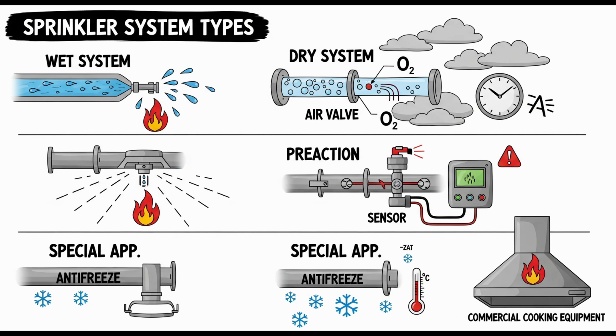And these alarms need to be reported somewhere. You can't just have a light blinking on the valve. No. These low or high pressure signals must notify building maintenance staff via an audible signal, or they must transmit a supervisory condition signal to the building's fire alarm control unit. This ensures personnel are alerted to investigate and rectify pressure issues before they compromise system operation. Okay, ensure someone knows there's an issue.